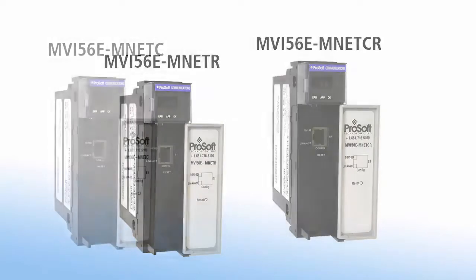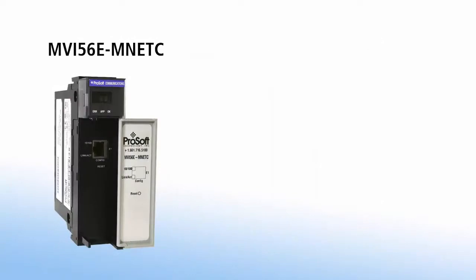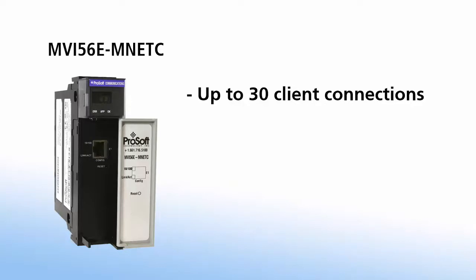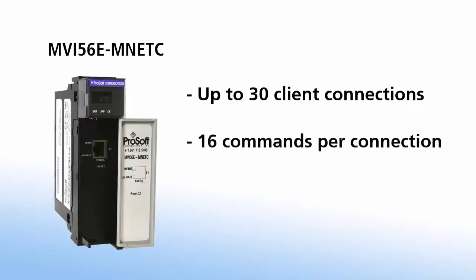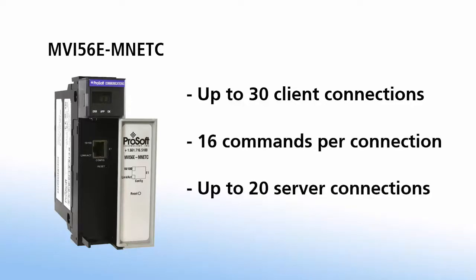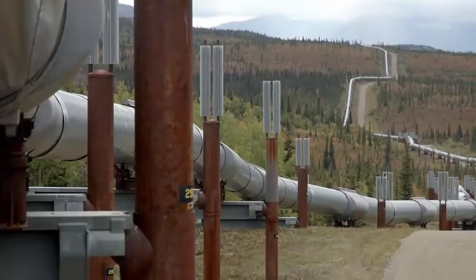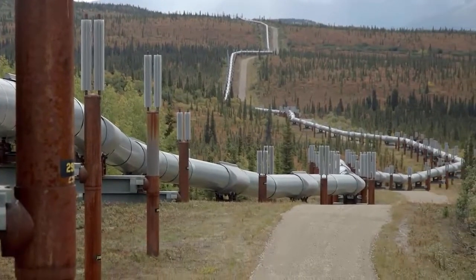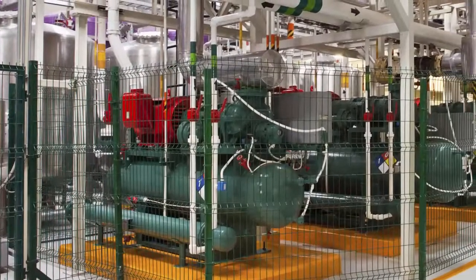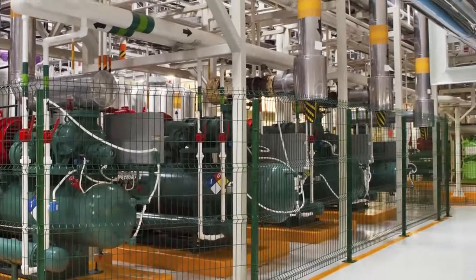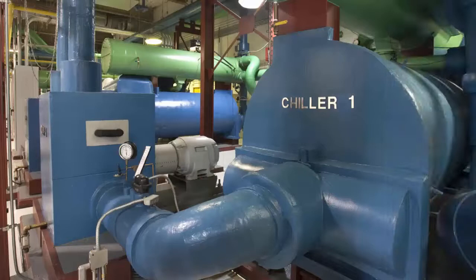The MVI56E-MNetC is our most versatile module, supporting up to 30 client connections with 16 commands per client, and up to 20 server connections. It's ideal for applications such as monitoring meters and valves on a pipeline or controlling power relays, electrical meters, compressors, or chillers. Anything where there are multiple devices to communicate with.